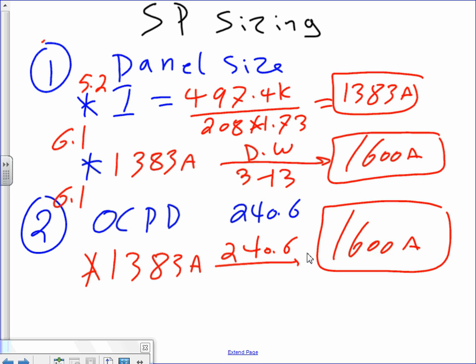Cool. So what size panel do we have, gentlemen? Switchgear or panel. We have a 1600 amp panel, and what size overcurrent device inside it? 1600. Almost always, guys, the size of the circuit breaker and the size of the panel will be the same, but not necessarily. You could have a 400 amp panel protected by a 200 amp circuit breaker. That's okay. That's why, when you become an engineer, you're always going to look at the size of the panel and the size of the overcurrent device. Smart engineers make them match. I mean, size your system so they can match. That's the best way to do it.